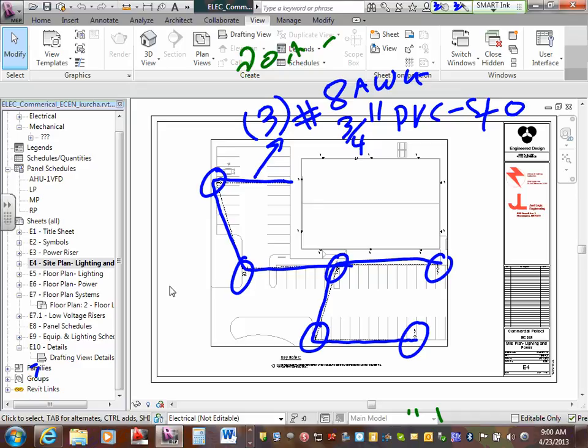Lump them all together. When it comes to your lights right here, guys, you're going to accommodate. There will be conductors. I don't know if they come with the fixture or not. We're going to assume it's not coming with the fixture. So you also need 3 conductors, number 12, 30 feet of them, to tie to your fixtures. Don't forget, guys, to accommodate for the pole. Yesterday, when I showed you the software, there is a place for poles, so you can take off a pole. You need to take this one as a branch circuit and as a trench. We're going to be trenching it.